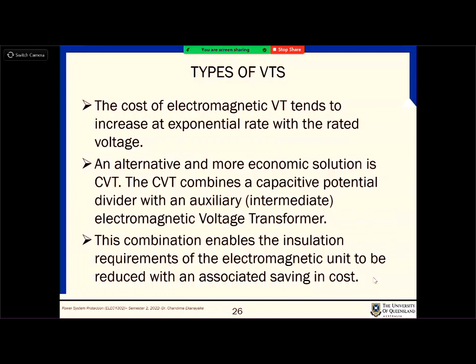There are various different types of VTs. Mainly they are electromagnetic VTs, and then there's something called CVTs, right? CVTs are capacitive voltage transformers. I will go into those 2 different types. What happens is that when the voltage level goes up, you can't just use the inductive VTs. The reason is the huge insulation cost, and you need very, very high insulation, so they combine the characteristics of a capacitive voltage divider and an electromagnetic voltage transformer.